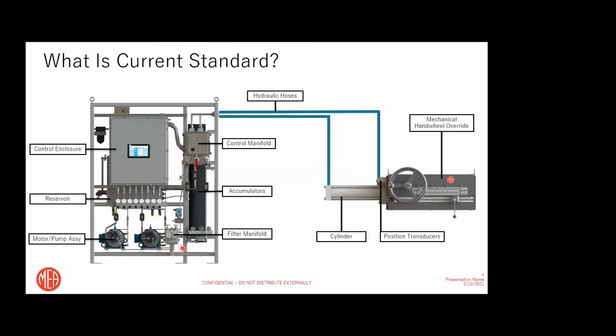So how it actually works: we take the hydraulic fluid from the reservoir, pump it through the motor pump assembly, basically build up hydraulic pressure, put it through the filter manifold and charge the accumulator. And then we use this charged accumulator energy, which is stored as hydraulic pressure, and send it through the main manifold, which sends the fluid into one side or the other side of the cylinder.